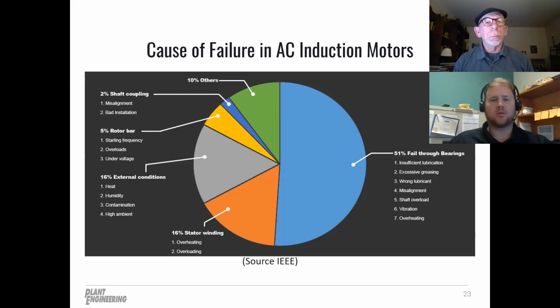The next leading cause of failure deals with stator winding issues, characterized here by short circuit or open circuit. These winding issues are caused by repetitive overloading or subsequent overheating of the motor. External conditions are next, with winding issues. That includes heat, humidity, and then contamination. And then a few other types of failure are listed. It's also worth mentioning that motor build quality plays absolutely a major role in motor reliability and long-term motor life. You can do everything right, but if the motor has quality issues from the factory, it still may fail prematurely, and that could be out of your control.